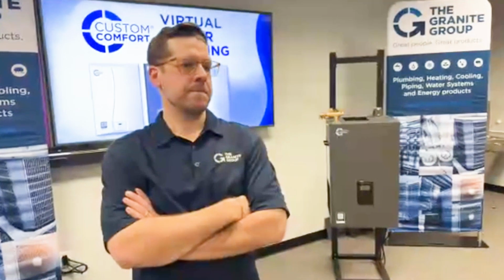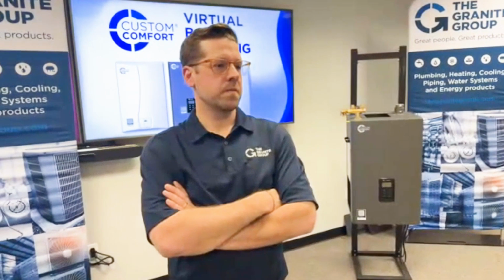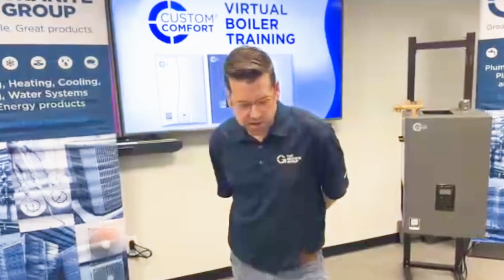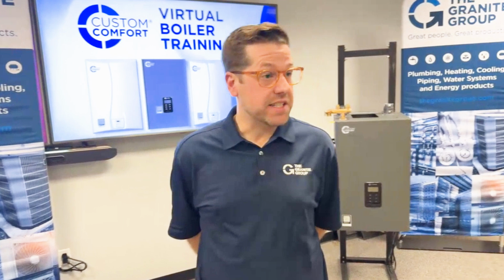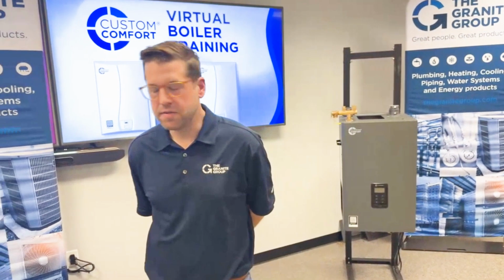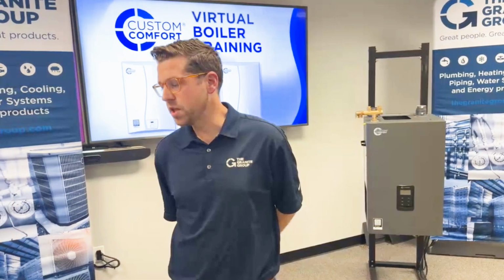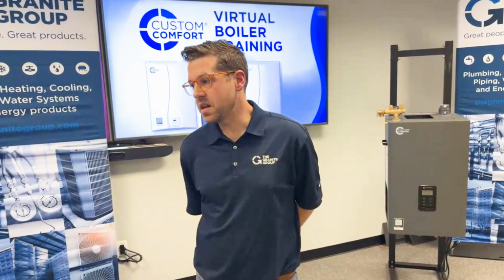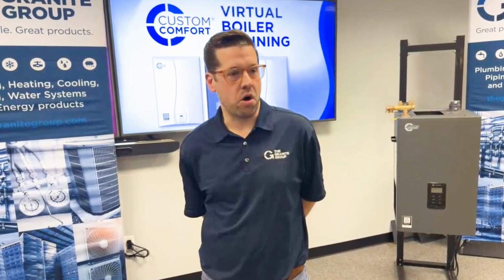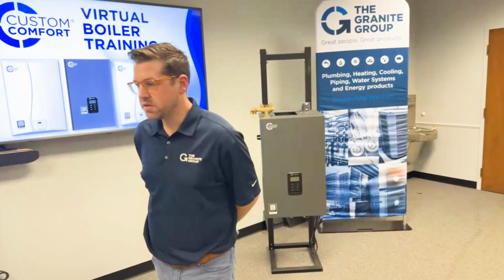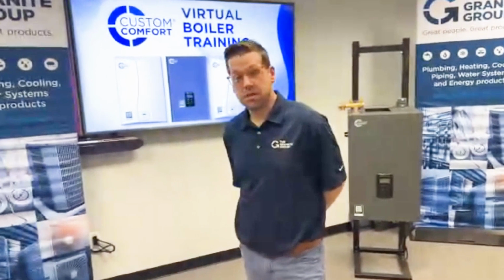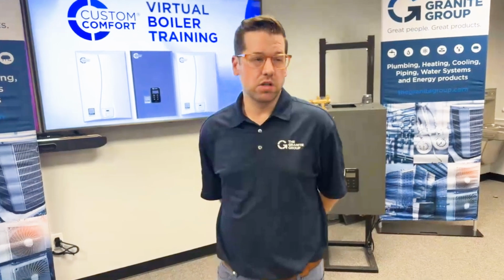So Al is wondering, can these boilers and combis be daisy chained together to get more BTUs? Yep. The question was, can these boilers be cascaded or daisy chained together if you were looking at a larger application? We can do that. It's going to be via a tekmar external staging control. Within the boilers themselves, the control boards don't have the capability to cascade, but we could do that externally with some type of tekmar control.